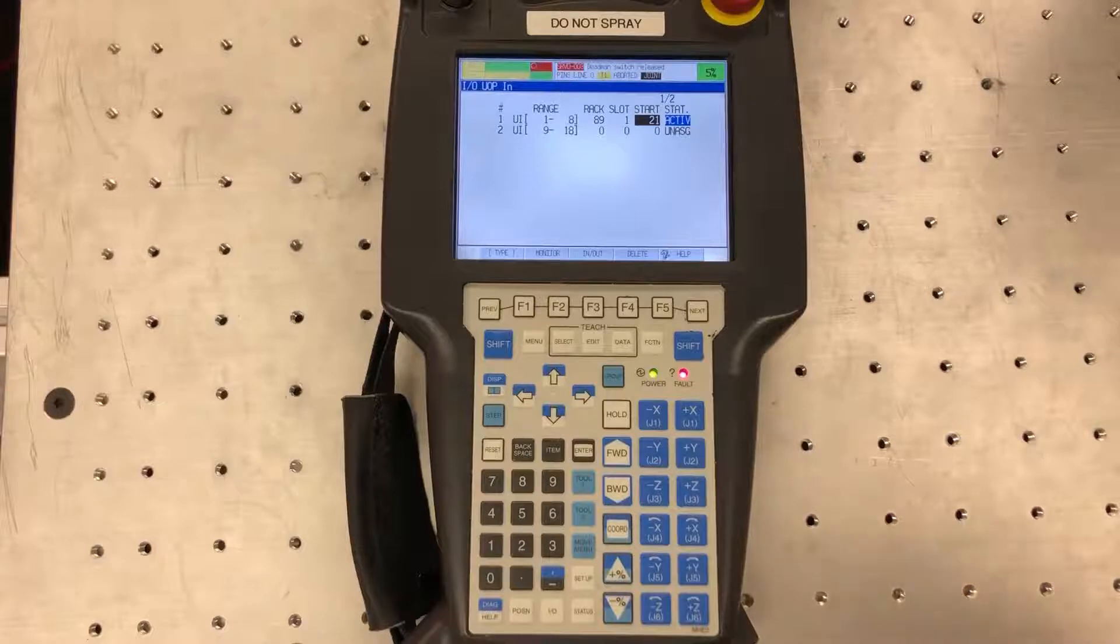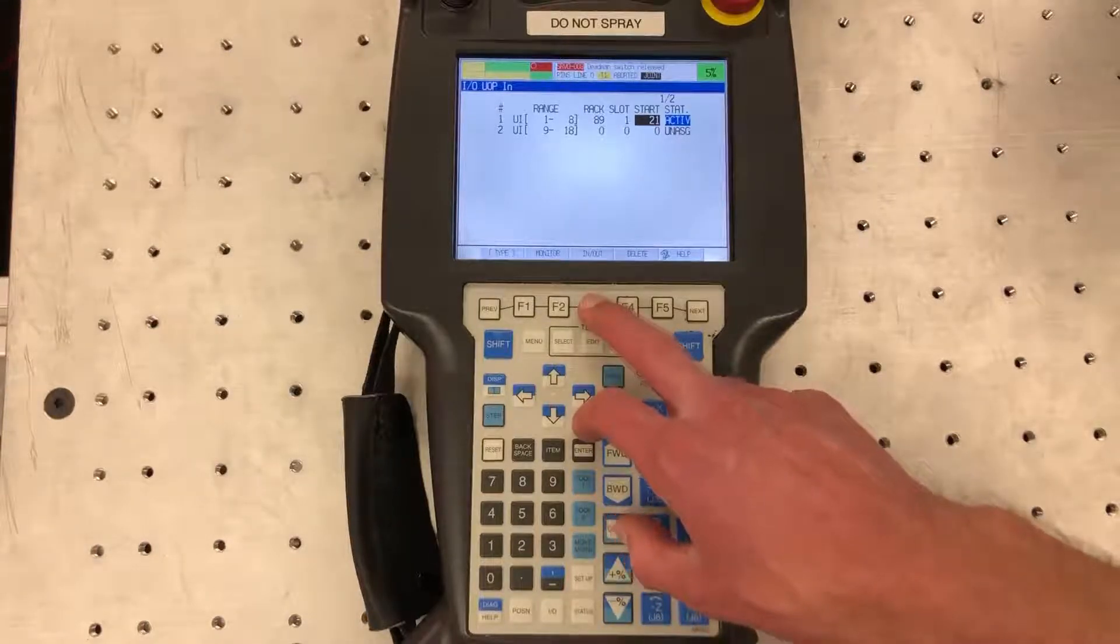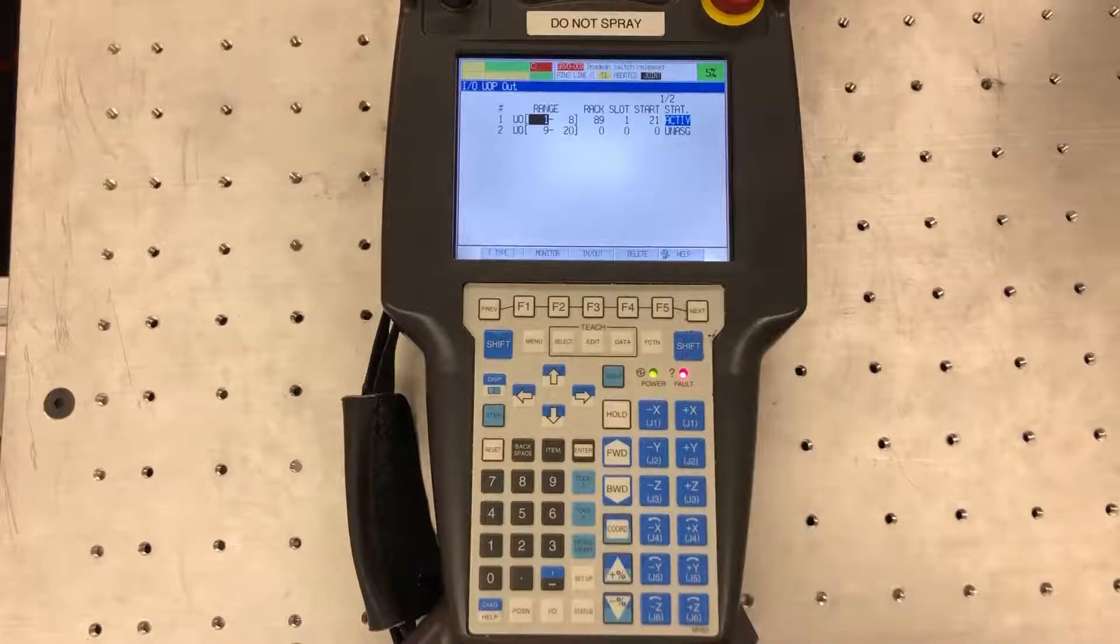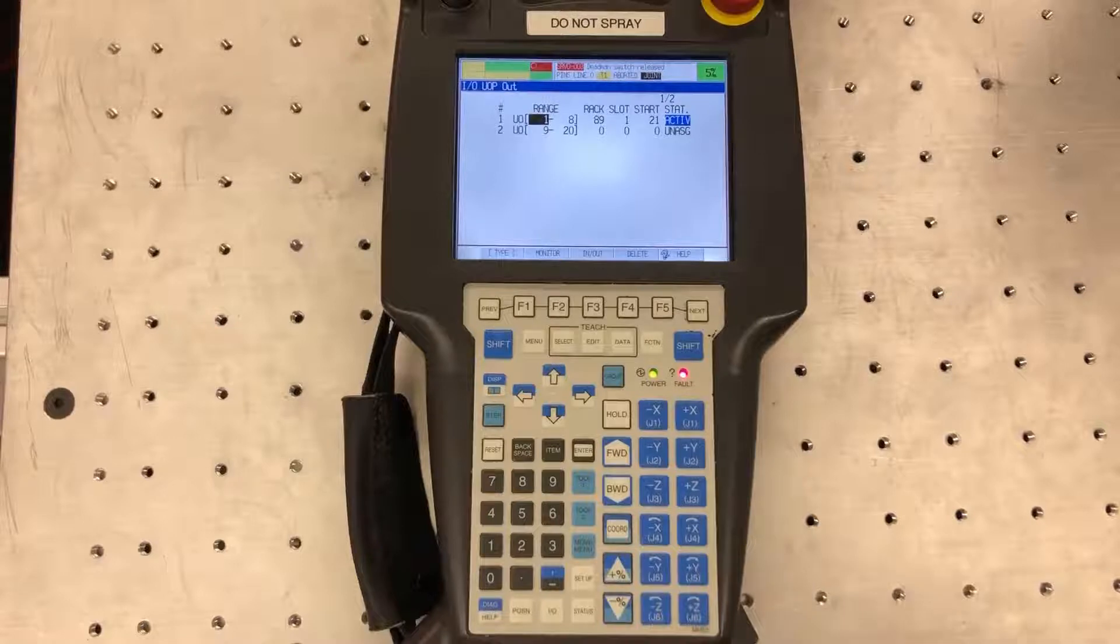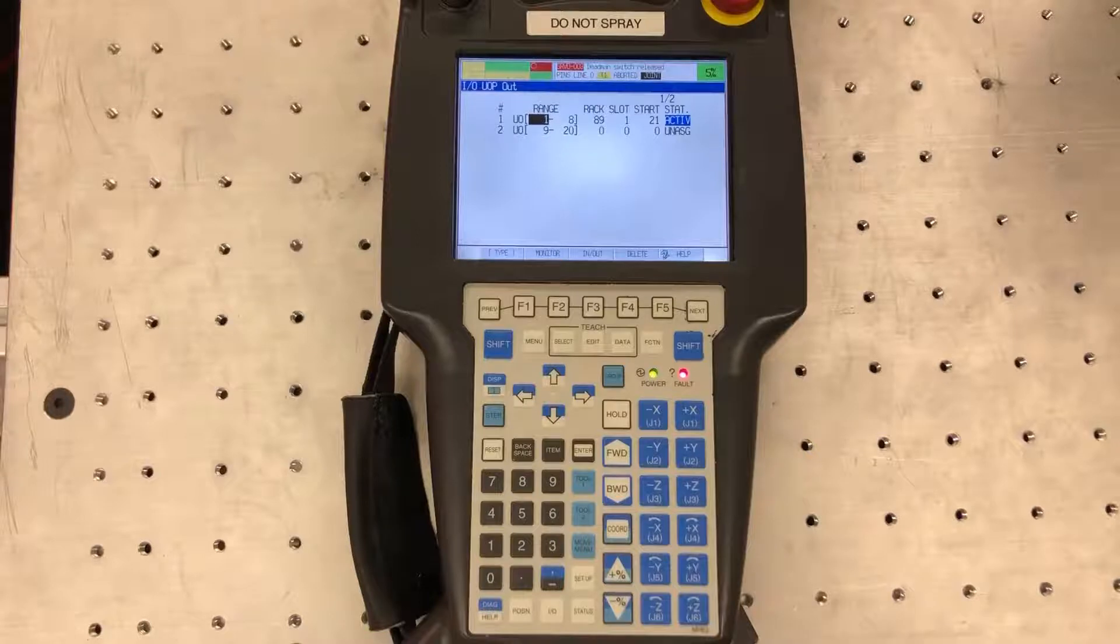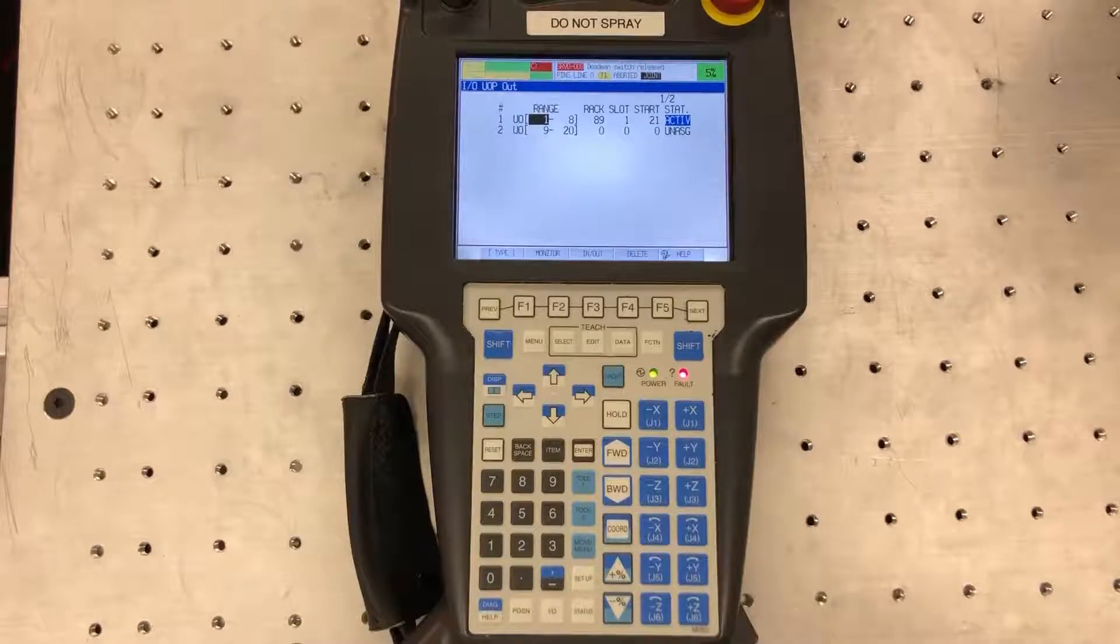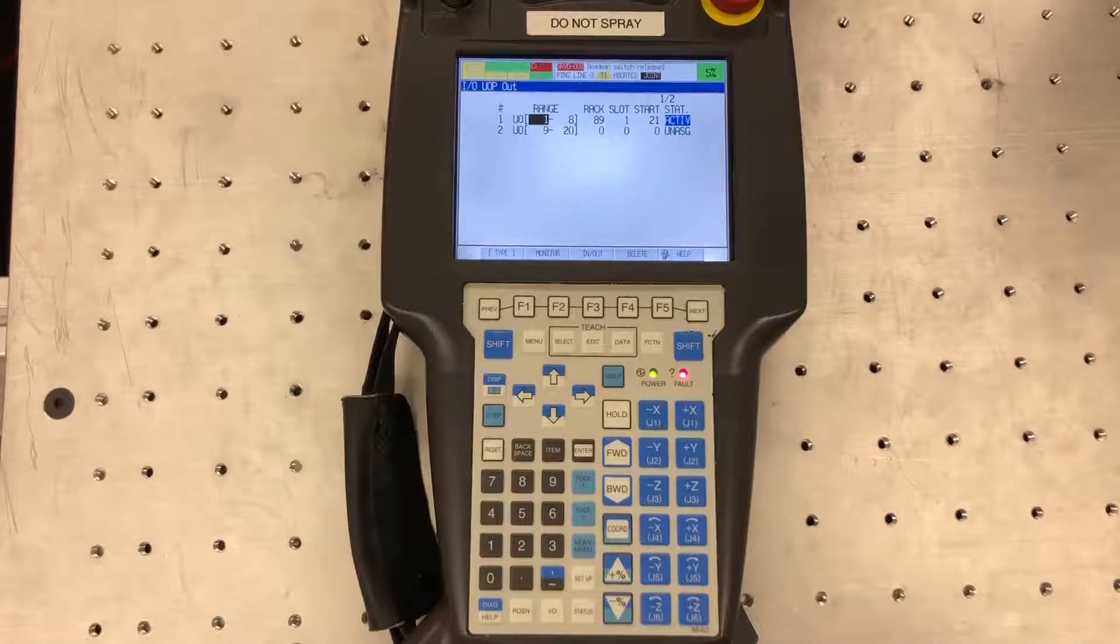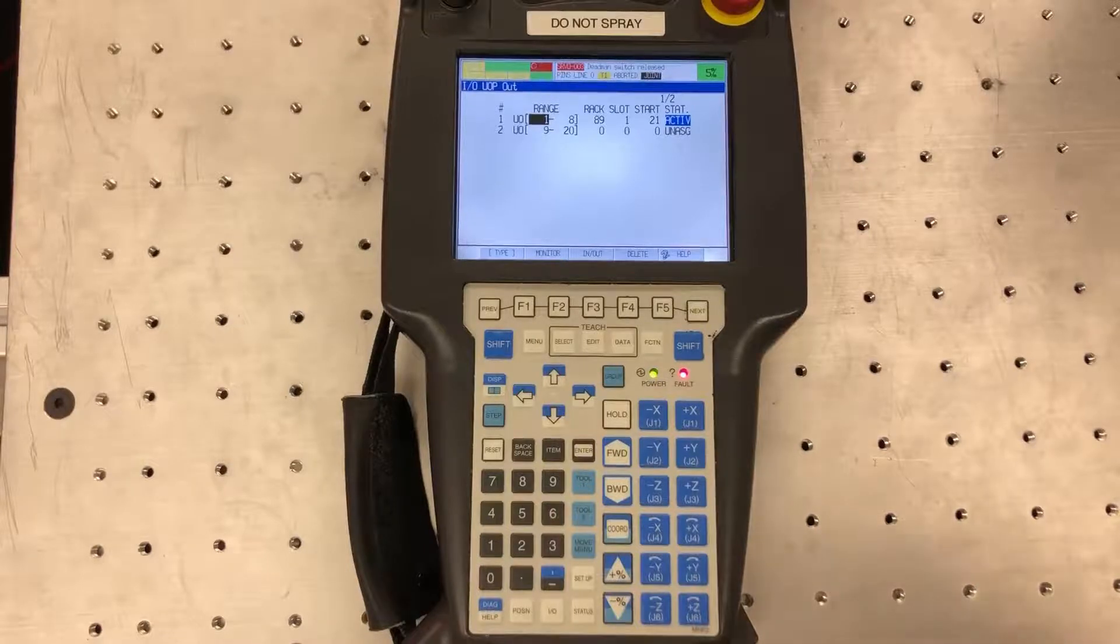Once we have this configured, we can go to the outputs side. So here's my output side. Again, range 1 through 8, I have a rack 89, slot 1, and start at 21. So you don't have to worry about the inputs and outputs overlapping because they're going to go in as different tabs on your PLC, right? Because they're going to be input tabs and output tabs, so don't worry about that.